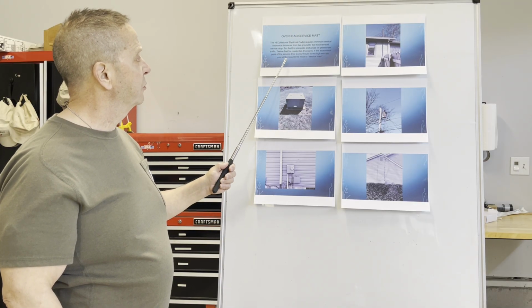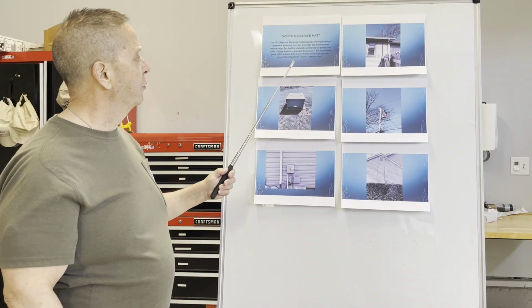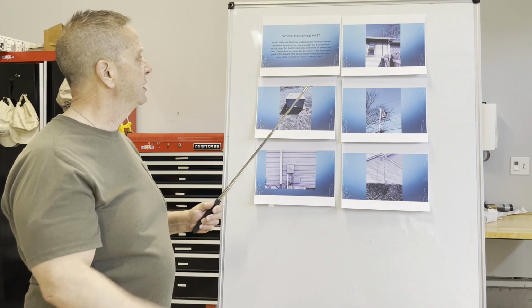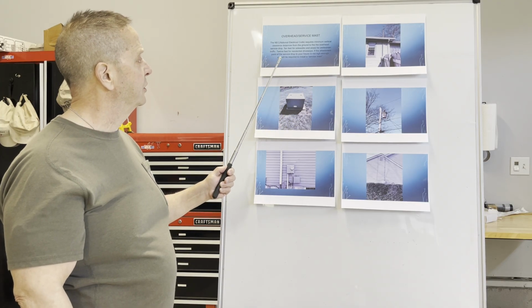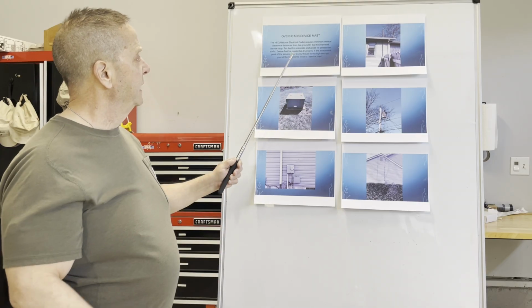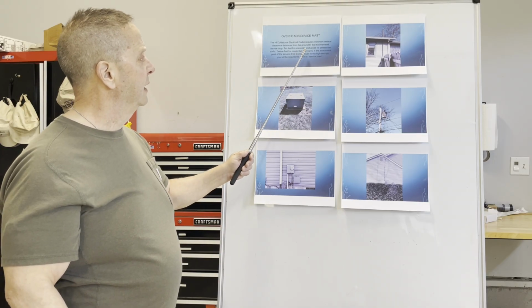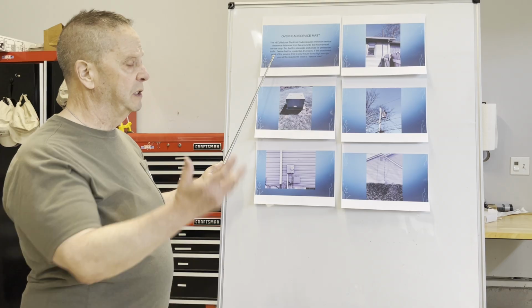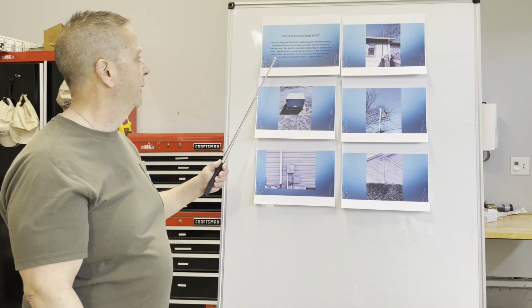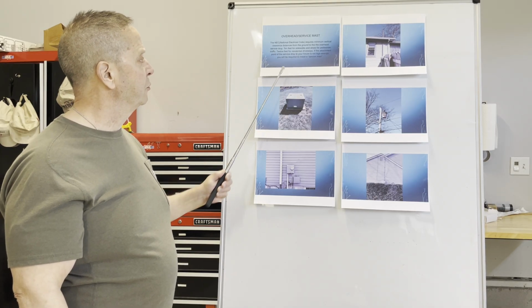The National Electrical Code, NEC, requires minimum vertical distances from the ground to the overhead service drop. You need 10 feet for sidewalks and areas where pedestrians can walk, mainly grass. 12 feet for residential driveways.